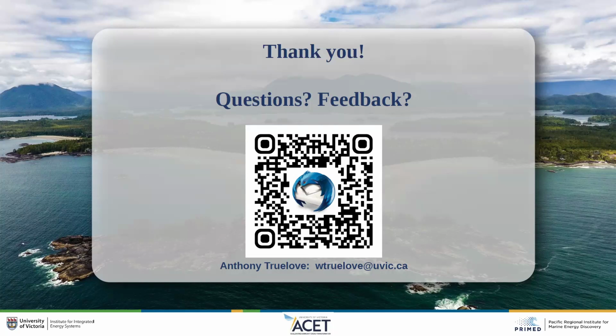Also we did something similar with Open DSS, compared against ETAP. We're going through the connection impact assessment with QEC on one of our projects. The contractor's taking too long, and we know they're using ETAP or something. Let's try and do our own model in Open DSS and compare it, so if the utility comes back and tells us we have to do all this stuff and invest in all these things, we have a sense where we can push back.